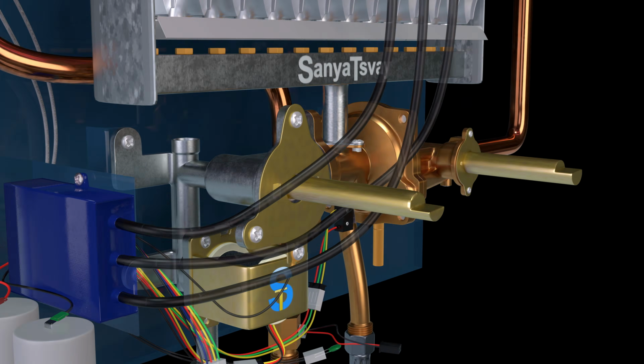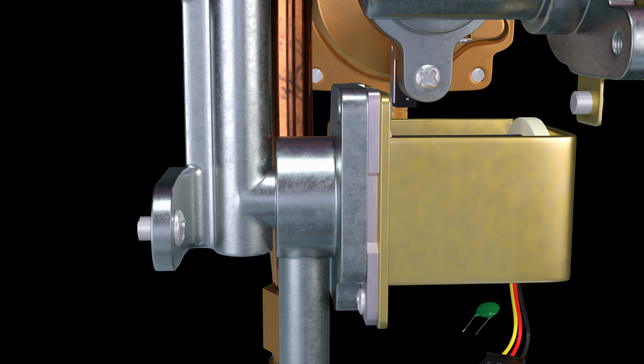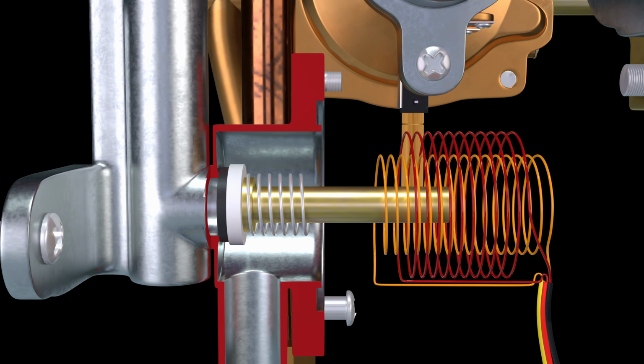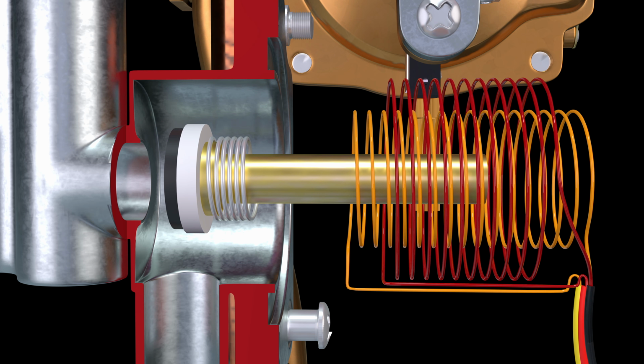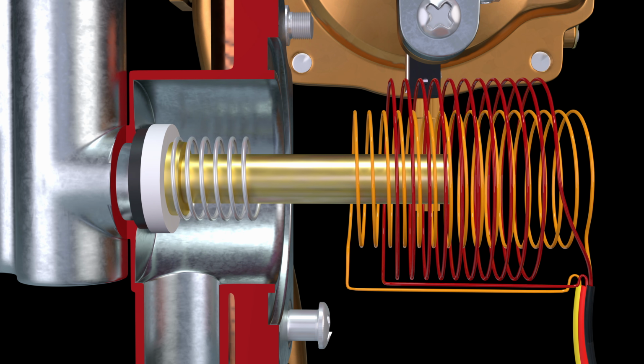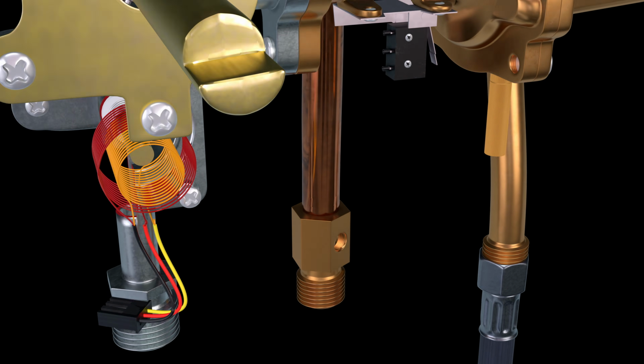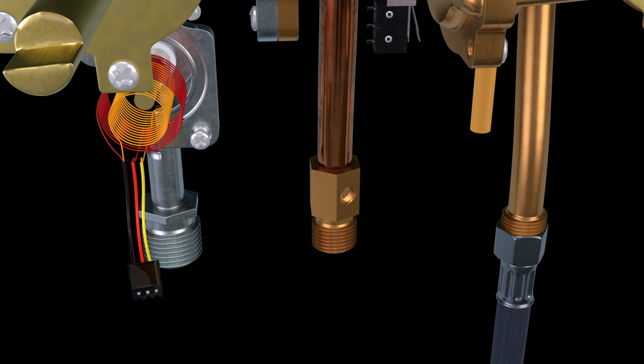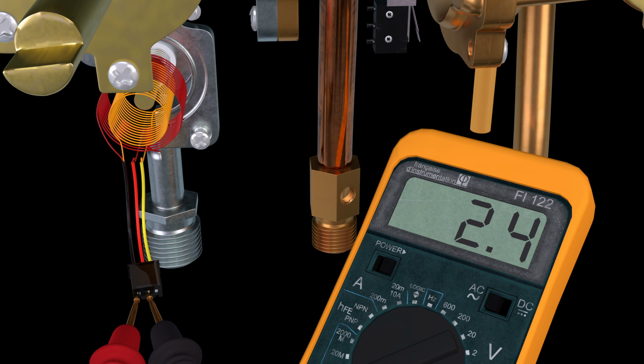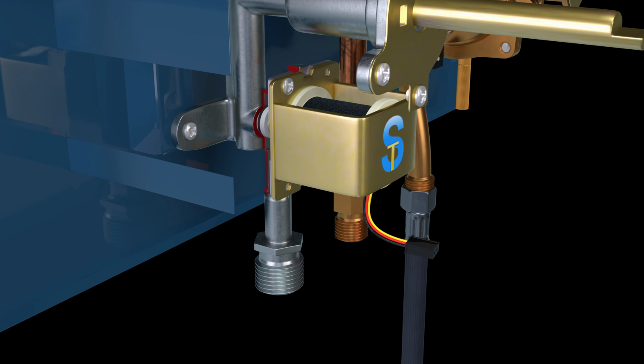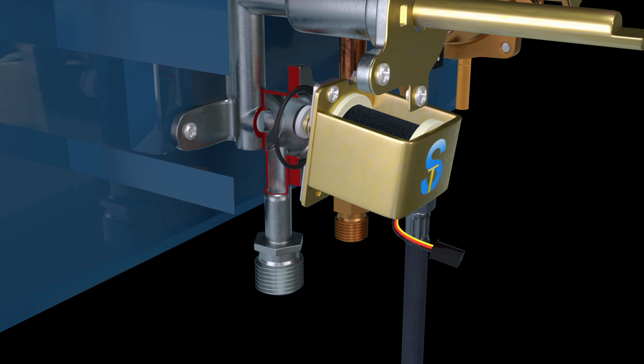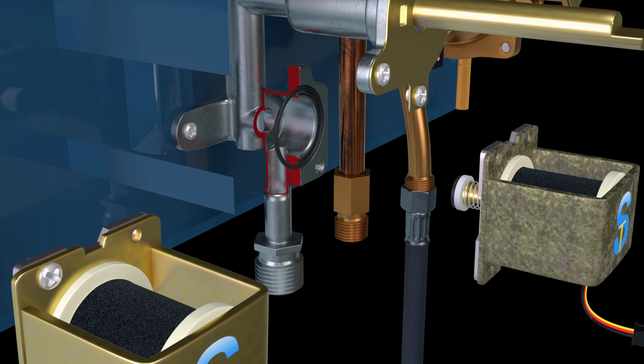I began searching for the cause and discovered that the problem was in the new solenoid valve. It has two coils, the actuating coil and the holding coil. The actuating coil worked. You could hear the solenoid click. The plunger was being pulled in, but the holding coil wouldn't keep it engaged and the flame went out. I checked both coils with a multimeter for an open circuit. Both were intact. But in practice, the valve simply didn't operate correctly. I reinstalled the old valve, and everything worked perfectly, as if nothing had happened.